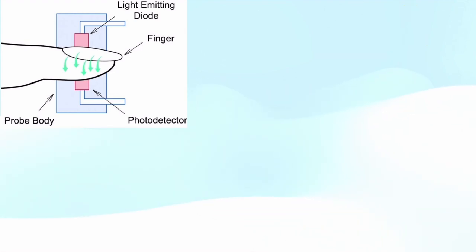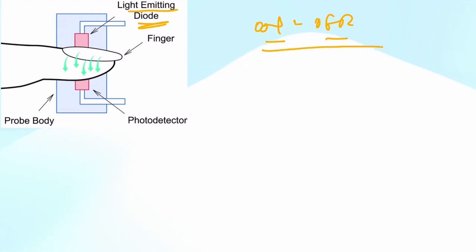So what happens? These two LEDs synchronously switch on and off intermittently, permitting the calculation of the absorption spectrum of these two hemoglobin molecules in a continuous manner, with almost 30 times on and off per second.